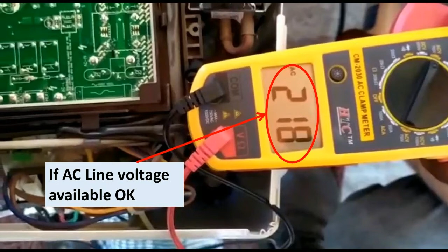For checking the fan motor, we have to check the voltage between neutral and the high, medium and low speed points. If the line AC voltage is available, then the PCB is giving output to the fan motor. In this way, if we check all these points, we will find out whether the PCB is okay or any defect is there.